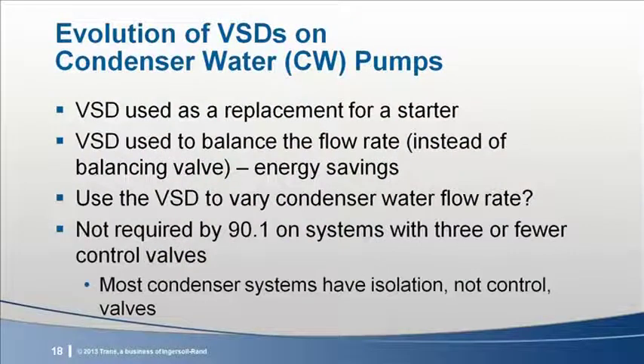Now, for systems that include not more than 3 control valves, 90.1 2010 has no requirements for variable speed drive performance. Since in most chilled water systems, the condenser system has isolation and not control valves, 90.1/2010 does not seem to require VFDs on condenser water pumps in chilled water systems.